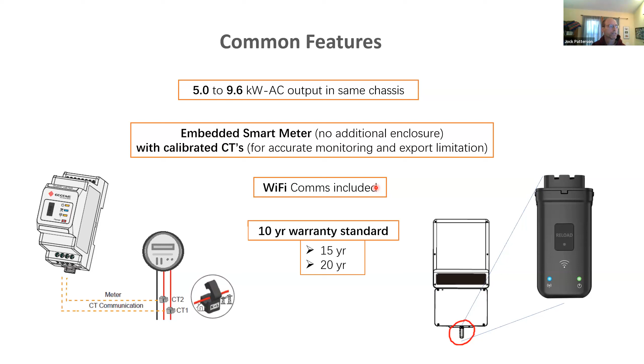When we look at just a PV inverter setup, the power flows in the orangish color are pretty understandable. So I'm going to focus on the red and blue dotted lines. In the upper left, we are circling around the rapid shutdown device to remind you that we realize that rapid shutdown is required often, and therefore, rather than getting a separate device, embedded inside, along with the smart meter, is a rapid shutdown transmitter. And you have 2 choices, a TIGO or an AP smart transmitter. So when you're ordering the product, don't just say, yes, I'd like that AMS 7600. Make sure you indicate whether you want the TIGO or the AP smart transmitter.